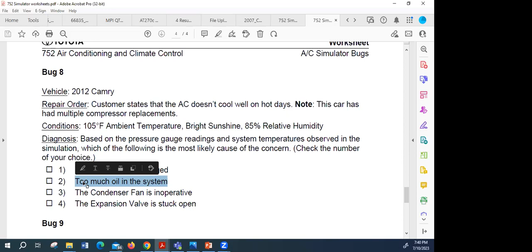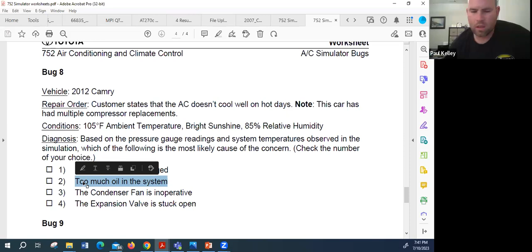Kind of, but I'm gonna help you out. If you have a lot of oil in there, doesn't that kind of take up the space that's supposed to be reserved for refrigerant? Yeah. And our cooling occurs because of refrigerant changing states, right? But when we have oil, oil doesn't change states, oil just floats around. So do we get any advantage of evaporation and condensation if it's oil? No. Nope.